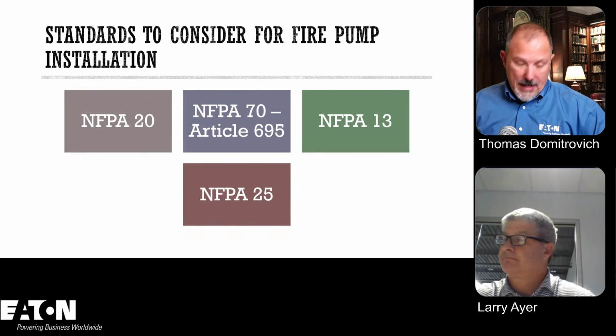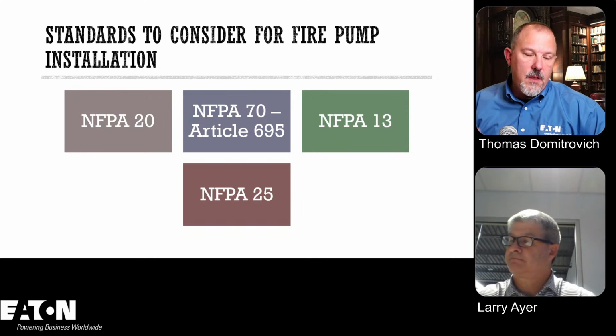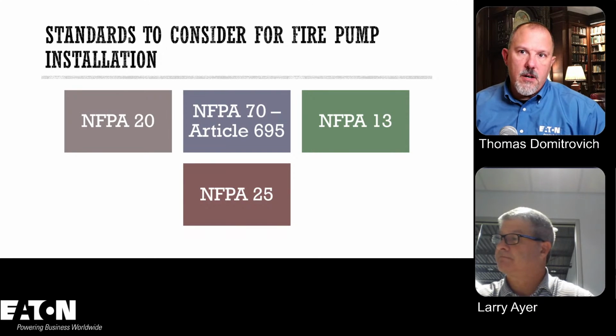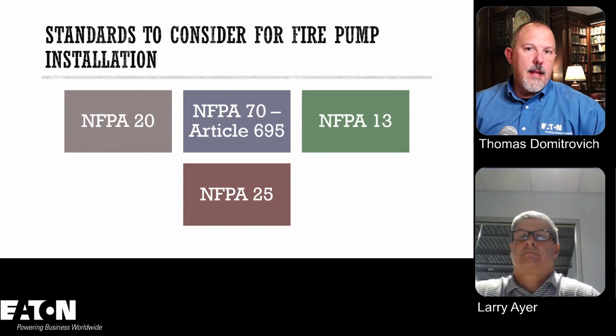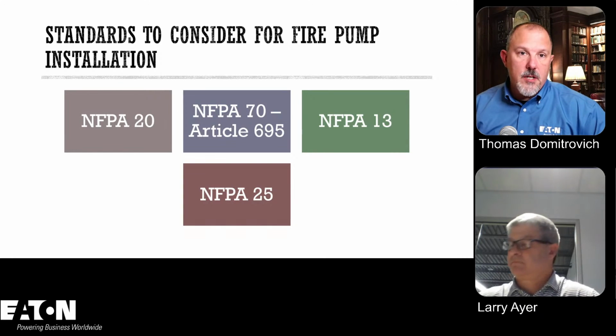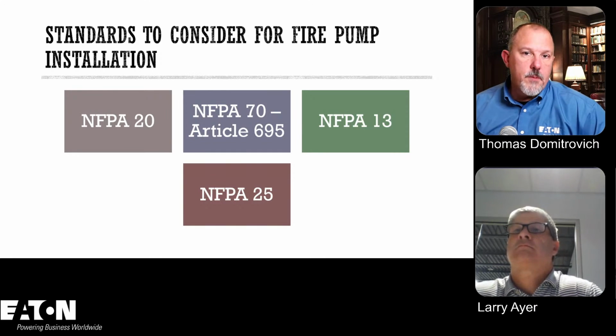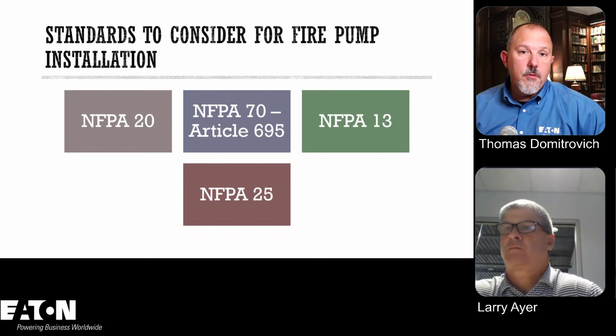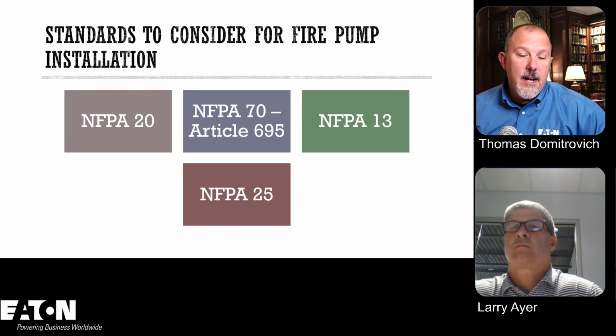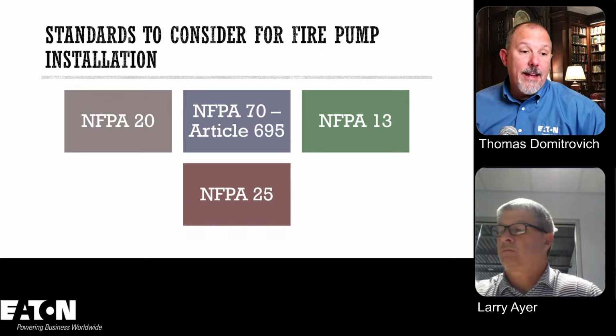testing and maintenance. So in my opinion, when you're working on a fire pump, because of how we design fire pumps, you're not allowed to have GFPE. You're not allowed to have these arc reduction technologies and things like that, because they're afraid of nuisance tripping or unwanted tripping. I think the electrical worker is in a difficult position there, that to establish an electrically safe work condition, you would have to go through a process to safely work if you're going to expose any energized parts in those applications. I've never worked personally on those. I don't know if anybody out there has.